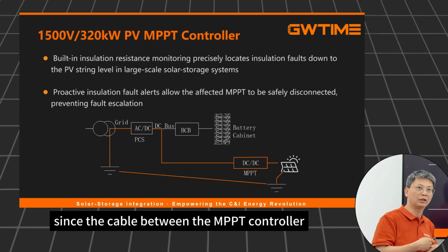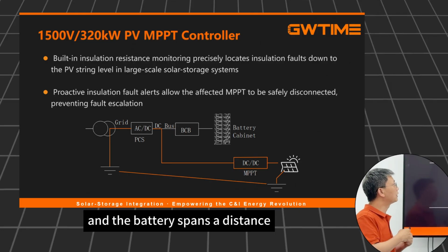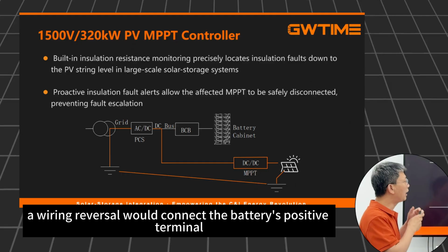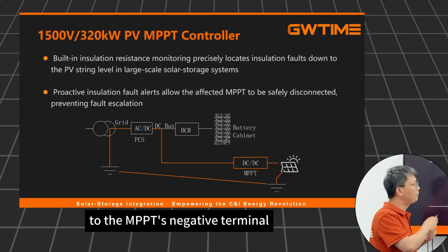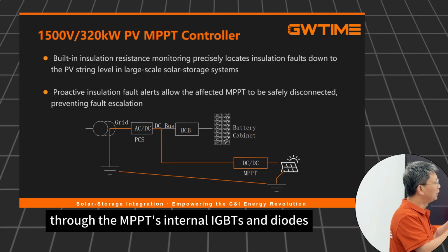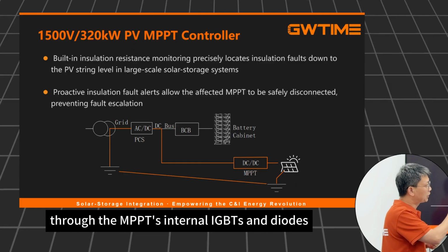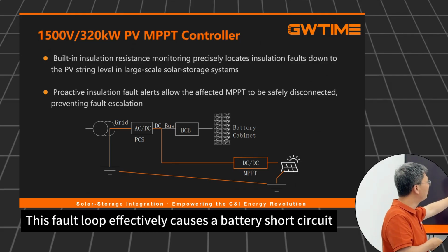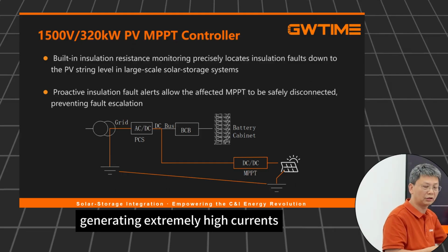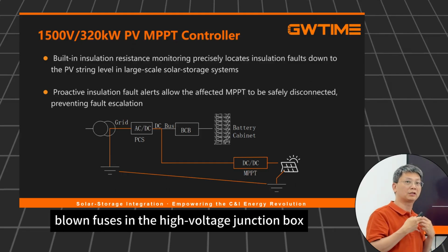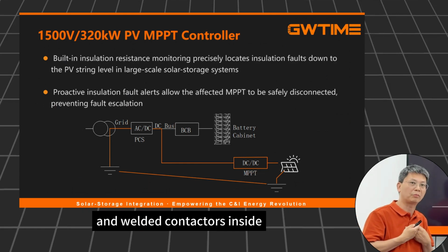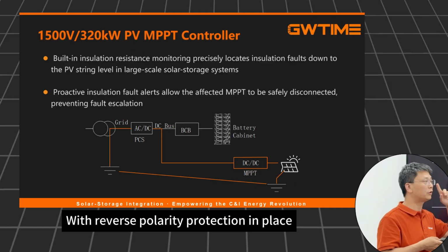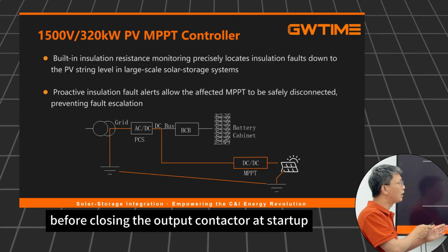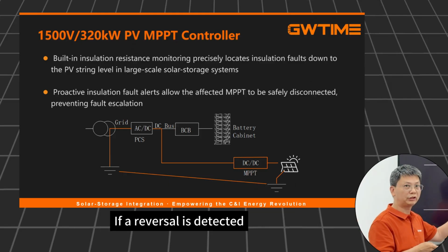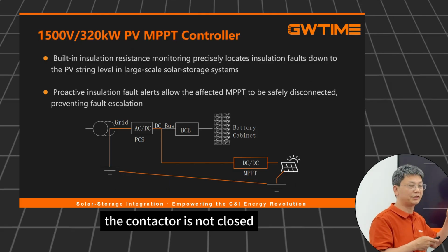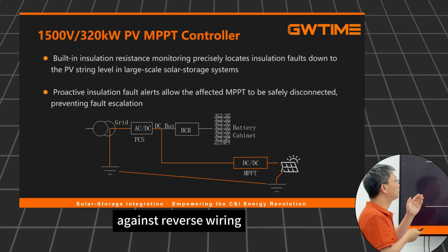Specifically, since the cable between the MPPT controller and the battery spans a distance, a wiring reversal would connect the battery's positive terminal to the MPPT's negative terminal, forming a fault loop through the MPPT's internal IGBTs and diodes. This fault loop effectively causes a battery short circuit, generating extremely high currents. The consequences can include blown fuses in the high voltage junction box and welded contactors inside. With reverse polarity protection in place, the system checks the voltage polarity before closing the output contactor at startup. If a reversal is detected, the contactor is not closed, thereby providing complete protection against reverse wiring.